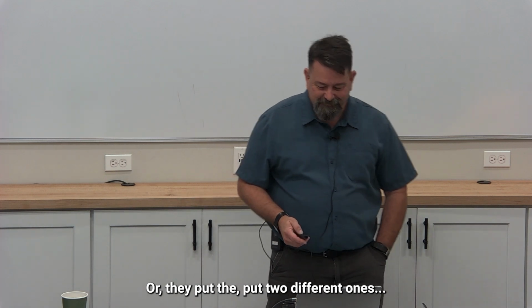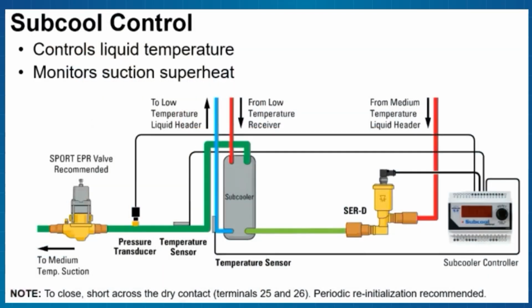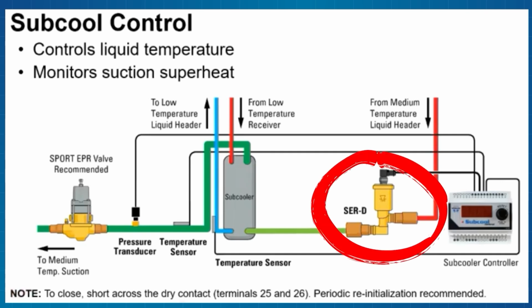Right, yeah, exactly. All right, so here's a little more modern setup. It's the same subcooler. Okay, and Kalos does these projects, right? We go in and take out the mechanicals and we drop in the electronic, all right? What's going on here? Super simple. We're just taking the two TXVs out. We're adding an electronic TXV. And of course, it has to detect superheat, so a pressure transducer and a temperature transducer. It's calculating superheat downstream and just opening and closing that valve.